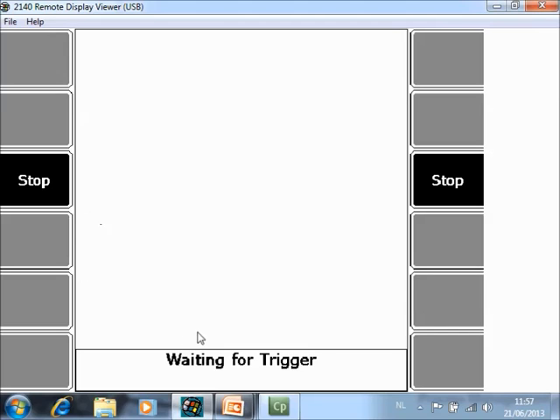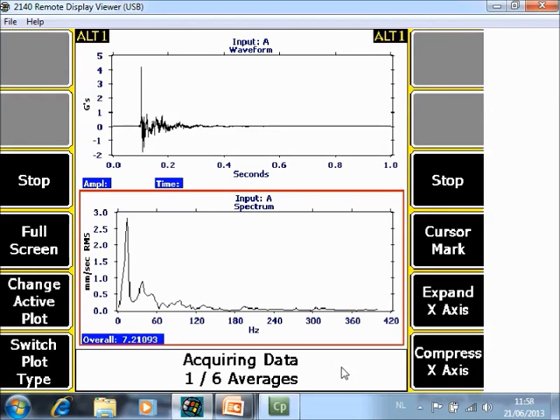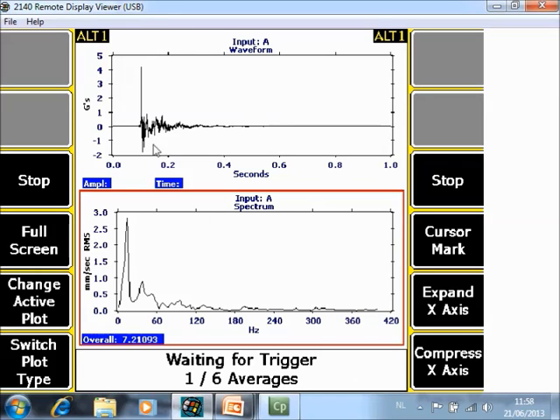Now you see here at the bottom waiting for trigger. That means the data collector is already measuring but is waiting for an impact. So I will now impact the installation, and he has captured his first impact as you can see here, and there is a spectrum calculated.